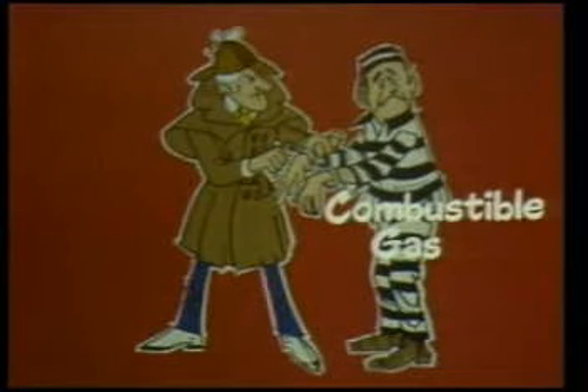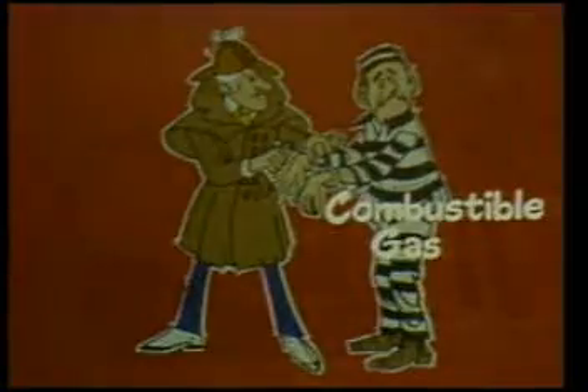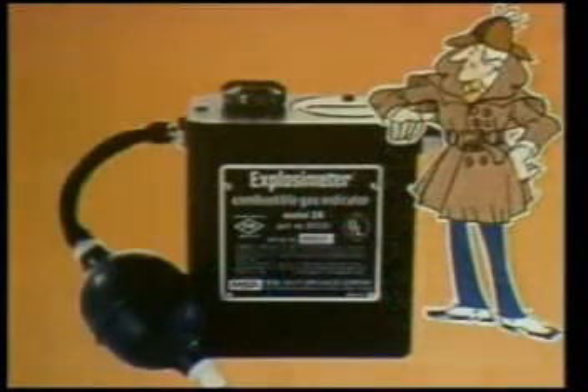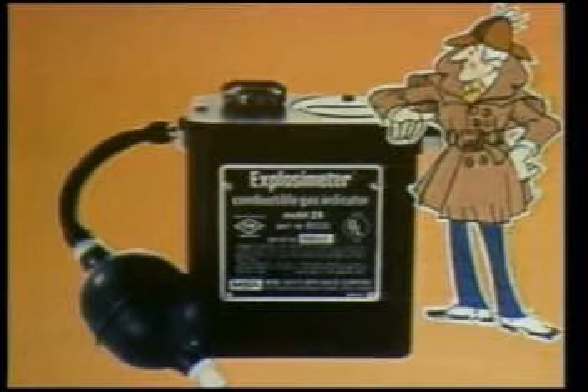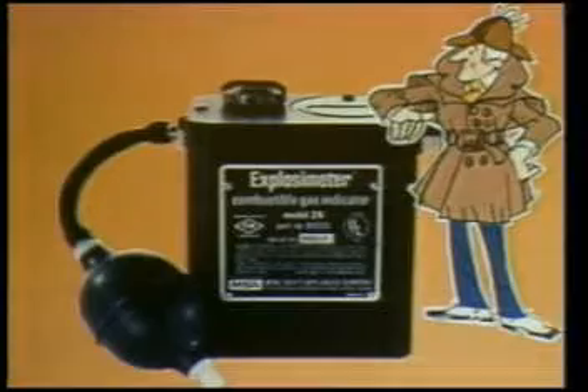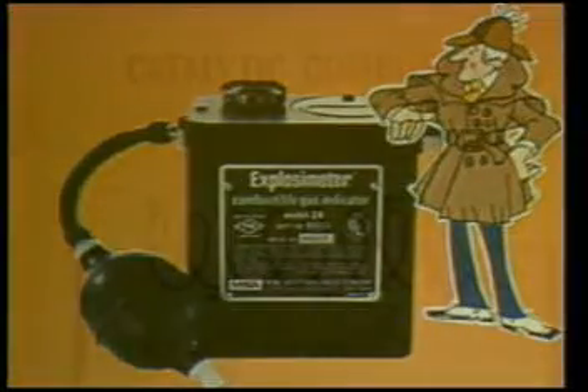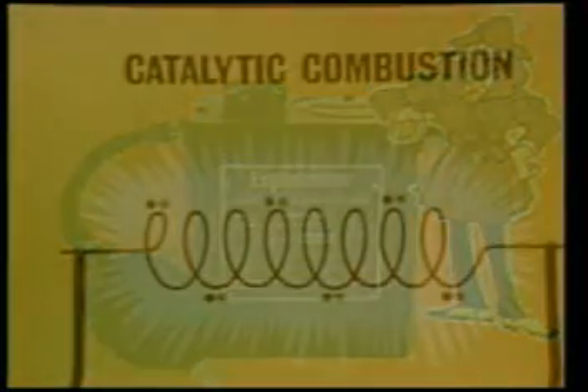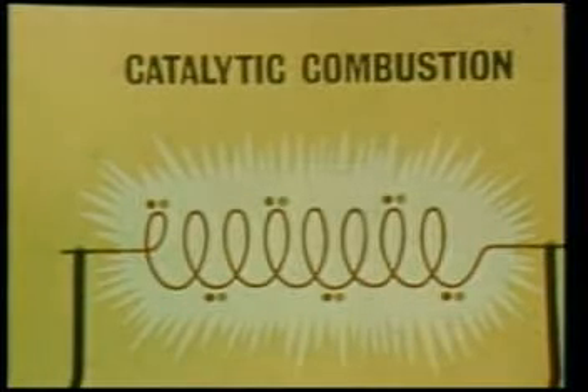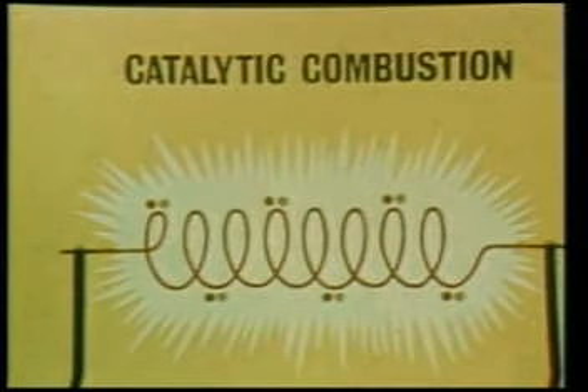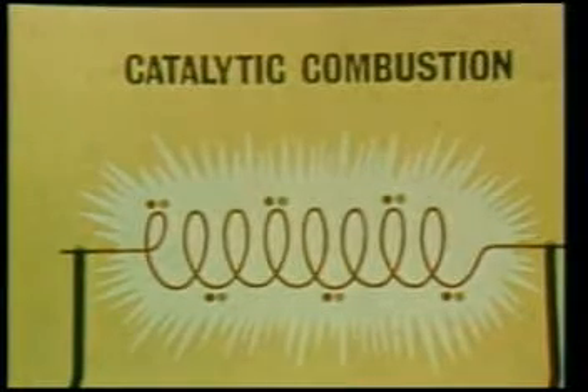Okay, now that we know more about our suspect, combustible gas, let's find out how this instrument called an explosimeter indicator works. As the name suggests, it's designed to detect the presence of explosive or combustible gases in the air. It's based on the principle that a measurable amount of heat is released when a combustible gas or vapor is burned. Here, the combustible is burned on a coil of platinum wire. The increase in temperature changes the electrical resistance of the wire.